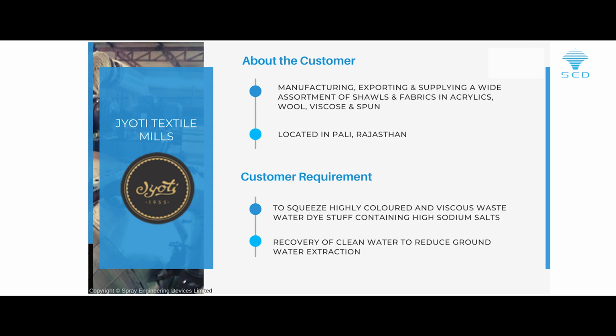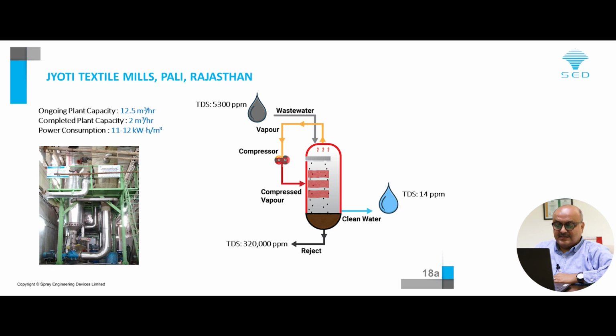This is in Pali. It is a Jyoti textile mill. In the Pali cluster, we have supplied many plants, and I think there are around 9 plants in Pali, where the individual textile owner is recycling the water and taking the condensate back into the process. And you can see, although the TDS is not too high in the Pali clusters, the problem is the color. And incidentally, after passing through this evaporator and getting clean water of around 50 TDS or something around 40 TDS, they are recycling it back into their process, by virtue of which they are able to get clean water, as well as an improvement in the quality of their dyeing process. They are very happy using this condensate for their dyeing process, and the concentrate is solidified in the dryers over there and is being rejected to the landfills.